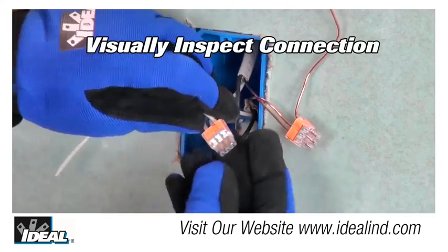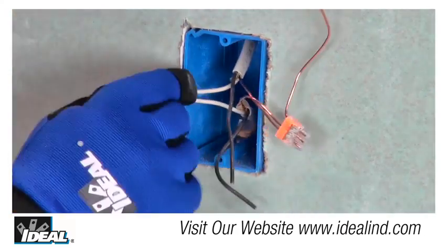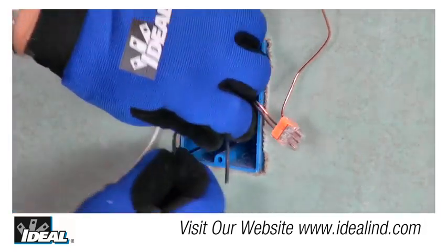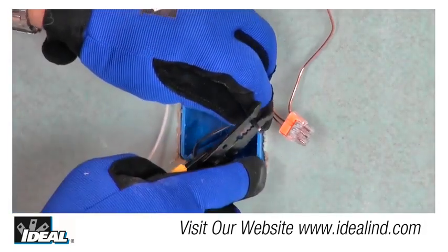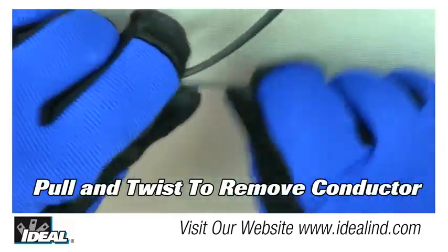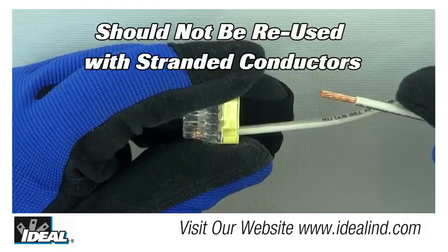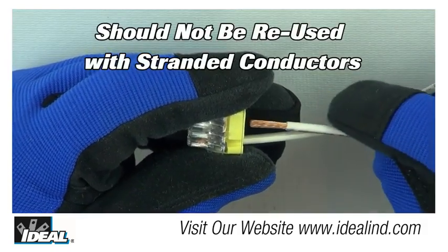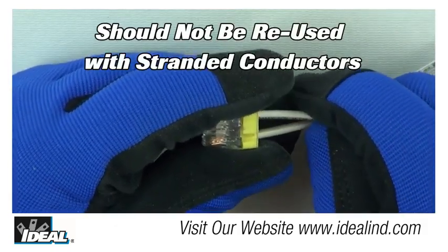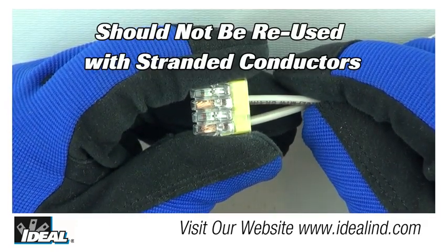The connector is reusable on solid wires of the same wire gauge or larger. If you are reusing the connector, cut and re-strip the conductors, then reinsert them into the connector. In order to remove a wire, pull and twist the wire back and forth until the wire is removed. IDEAL wire connectors should not be reused on stranded wire, as strands may become damaged or break free and become lodged inside the connector.